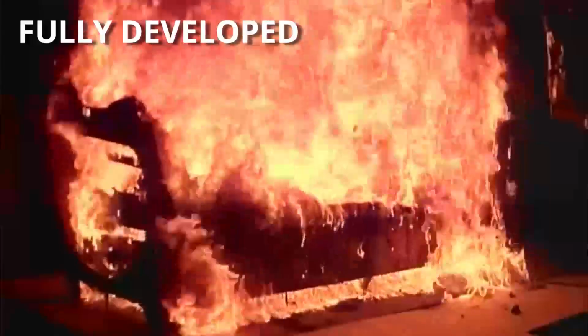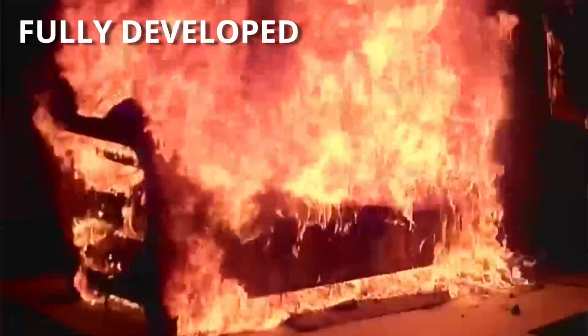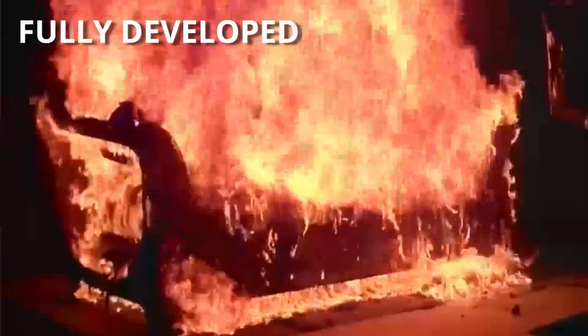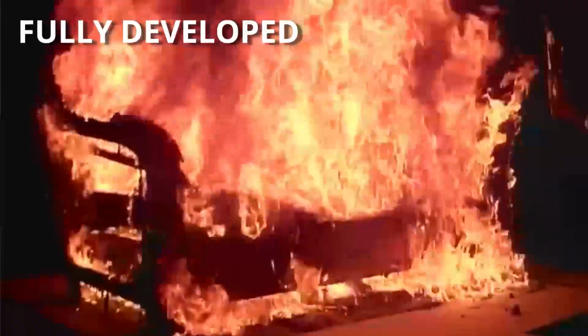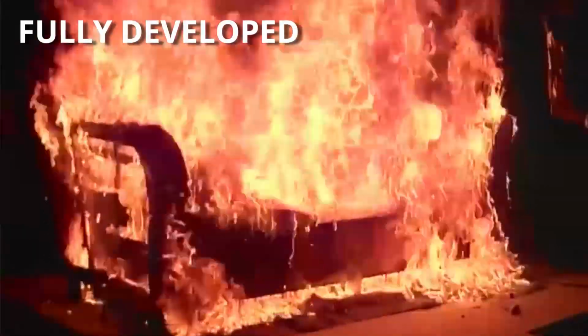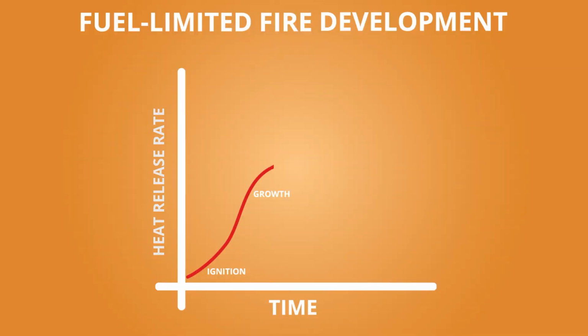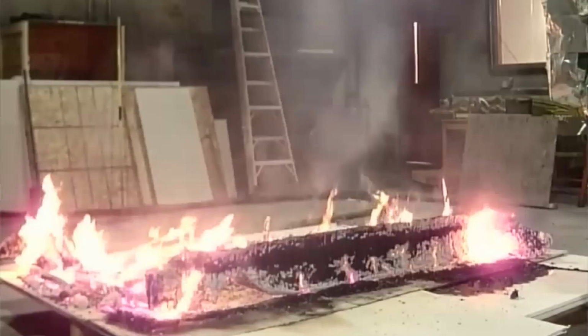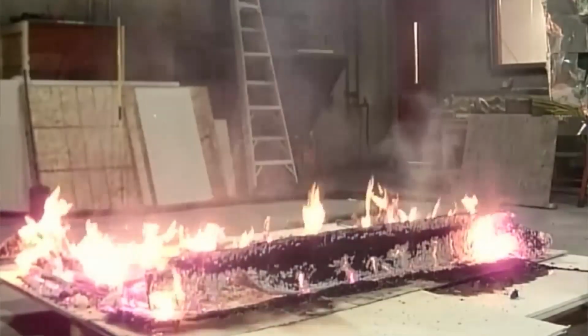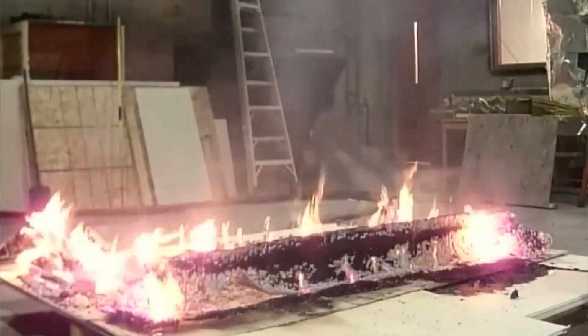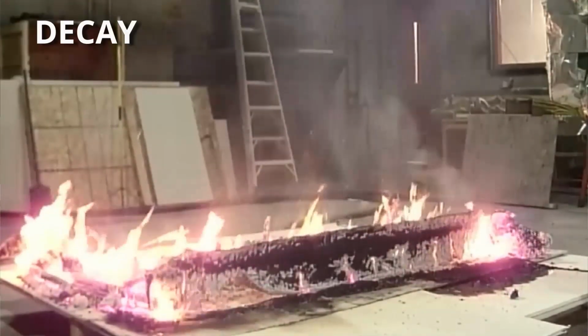During this stage, all the available combustible materials have been ignited and are actively burning. The lack of additional fuel limits the fire's growth. The fire produces the highest heat release rate during this stage of development. This is the peak size or hazard of the fire. As the amount of the available fuel is reduced, the fire enters the decay stage.